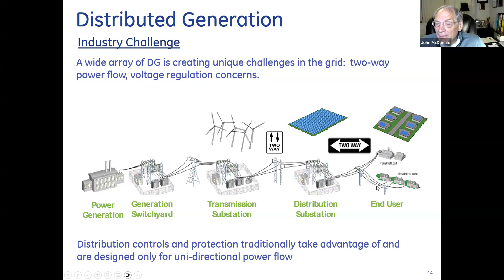So some of the challenges with electricity flowing in two directions is, for instance, protection ratings may not match fault currents. When we set the protective relays, we first do a short circuit study. We model the grid in different places, and we say, if there's a fault, what's the expected magnitude of the fault current? Well, when we do that modeling, we only look at the source side contribution to the fault, from top down to the fault. We typically feel that the load side contribution is negligible, and we don't consider it. But the problem is, if we have a high penetration of, say, rooftop solar or high penetration of PV panels on the distribution part of the grid, we could have a significant load side contribution to a fault. If a fault occurs when the sun is brightly shining, there could be a significant contribution.